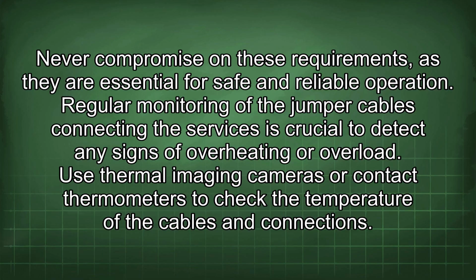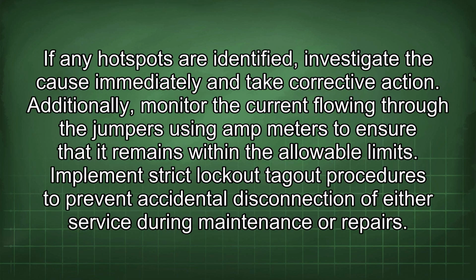Use thermal imaging cameras or contact thermometers to check the temperature of the cables and connections. If any hotspots are identified, investigate the cause immediately and take corrective action. Additionally, monitor the current flowing through the jumpers using ammeters to ensure that it remains within the allowable limits.